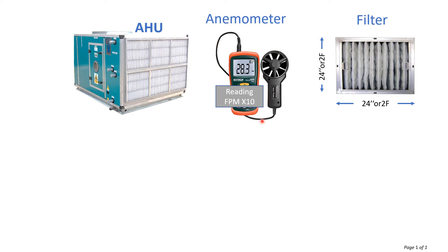Generally we take the reading on the AHU suction section, or you can say it is on the filter side. First, you set the anemometer to FPM mode. FPM is feet per minute mode, and then start taking readings on each filter.